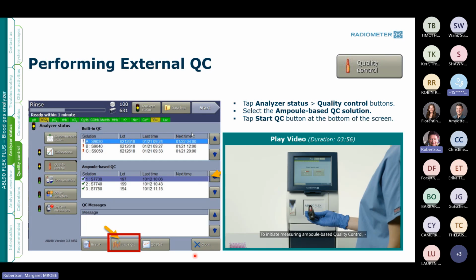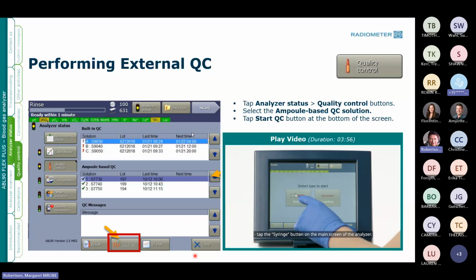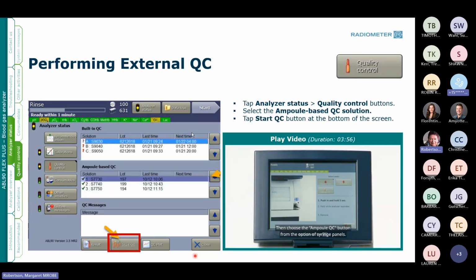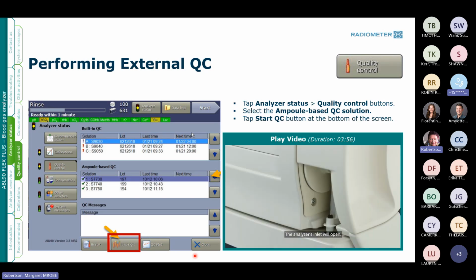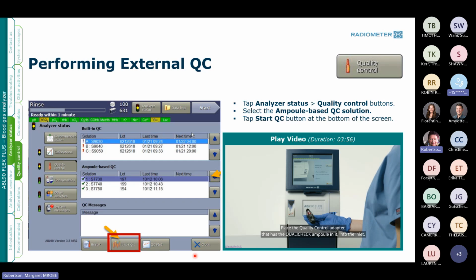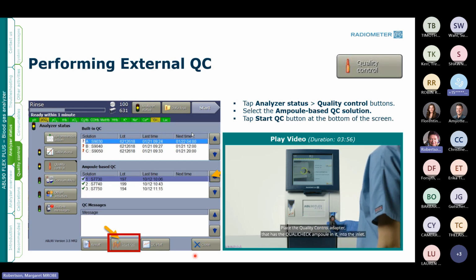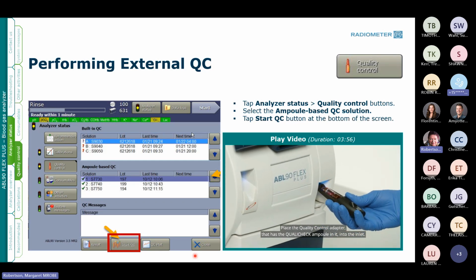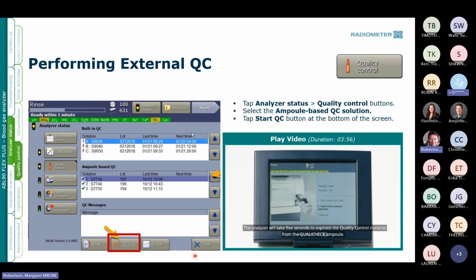To initiate measuring ampoule-based quality control, tap the syringe button on the main screen of the analyzer. Then choose the Ampoule QC button from the option of syringe panels. The exact workflow on the screen may depend on your analyzer settings. The analyzer's inlet will open. Place the quality control adapter that has the QualiCheck ampoule in it into the inlet. The analyzer will take 5 seconds to aspirate the quality control material from the QualiCheck ampoule.